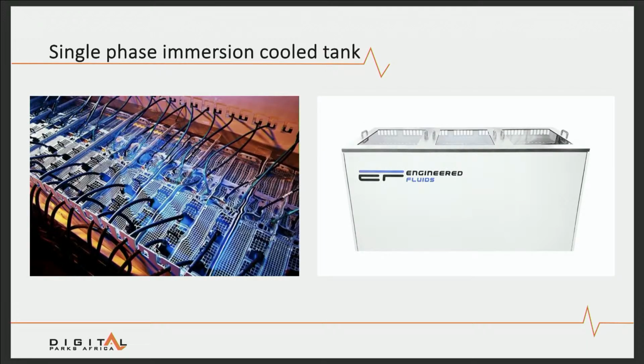Some more pictures here. You see typical examples of these tanks. And in data center environments where you have to utilize liquid cooling because of high power densities, you would have a number of these horizontal racks sitting on the floor. Already you can see one of the cost savings would be that you don't need the raised floor anymore because you're not passing any air underneath the racks anymore, the servers. Basically, you have a row of these tanks standing in a section of the data center.